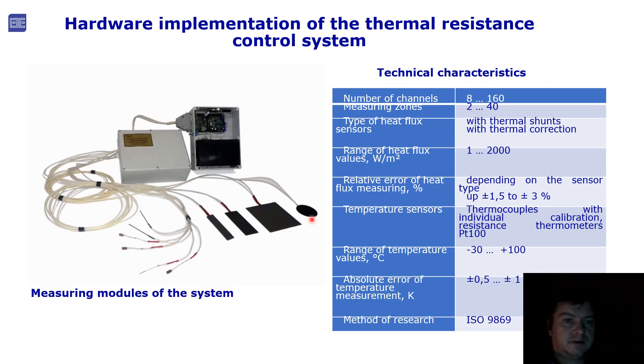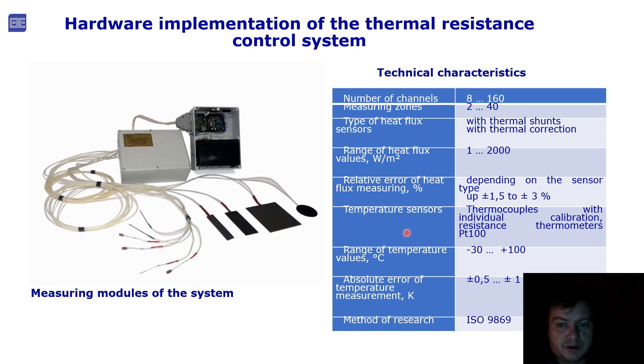On the slide is presented the hardware implementation of the thermal resistance control system. Each module has eight channels and can be expanded to a maximum of 160 channels, with temperature sensors providing from two up to 40 measurement zones. The system uses corresponding heat flux sensors and temperature sensors — thermocouples with individual calibration and resistance thermometers.